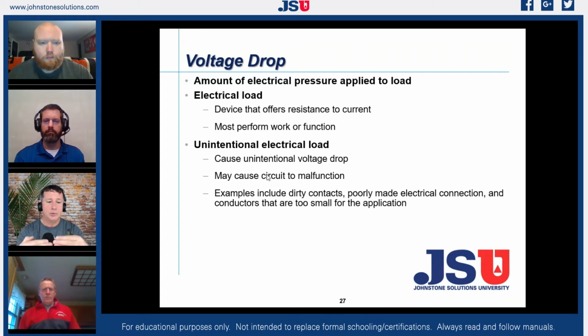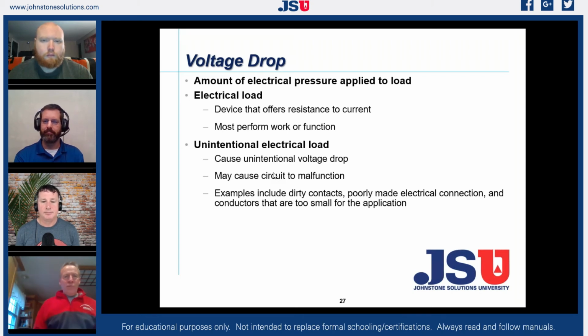And so as our contact points start burning and arcing across each other, we actually lose our surface contact to the point where we turn our contact points into a resistor. And anytime that we have a resistive load, we are going to convert our electrical energy into heat energy. That's why we burn up contact points on relays and contactors. And to be honest with you, Clifton, it's kind of a compounding effect, because as you eliminate the electron flow, you increase the load. So the amperage starts going up on the back end, and you start pitting it even worse. So it compounds itself over time.